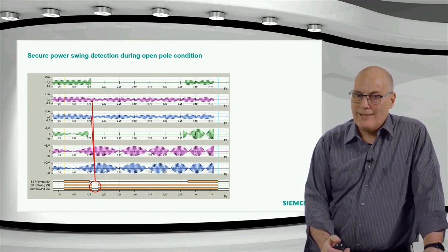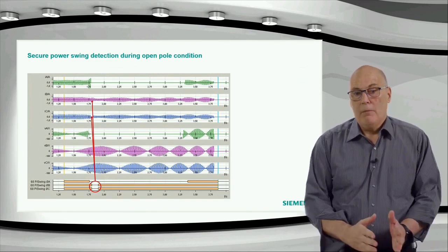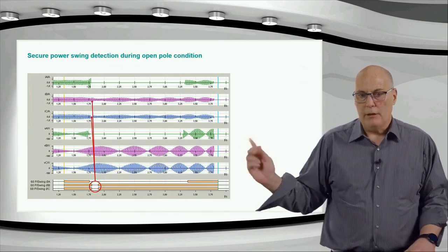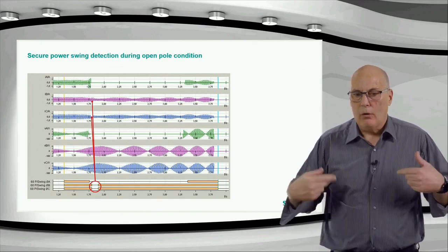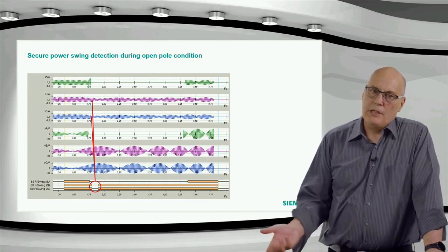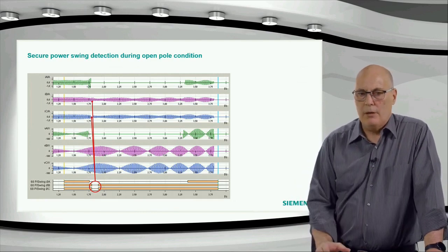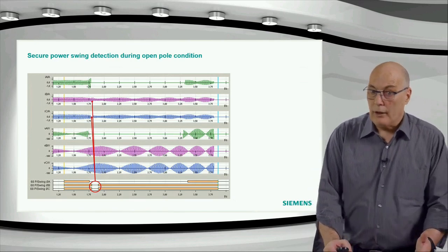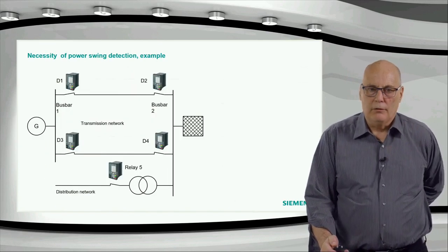The power swing blocking is still active there, and that's why in SIPROTEC 5, you will not see a gap there. But in SIPROTEC 4, there was an 80 millisecond timer. What you see is the measurement drops off due to the jump, but there's a delay on reset of the function of 80 milliseconds, which bridges that drop off in SIPROTEC 4. In SIPROTEC 5, we changed the signal output. The signal output includes the stability timer, so you don't see the gap in SIPROTEC 5. The functionality is the same, you are still blocking in that gap, but you get some more consistent information in SIPROTEC 5.